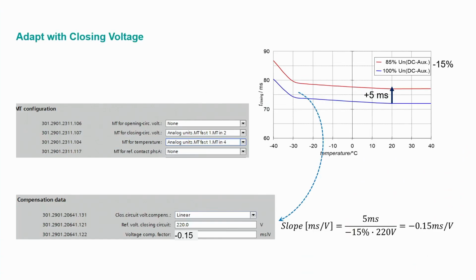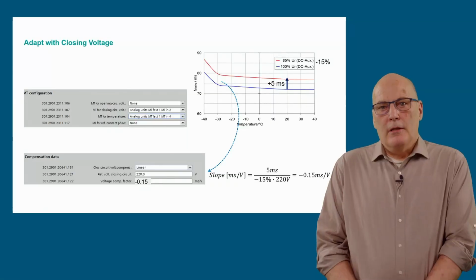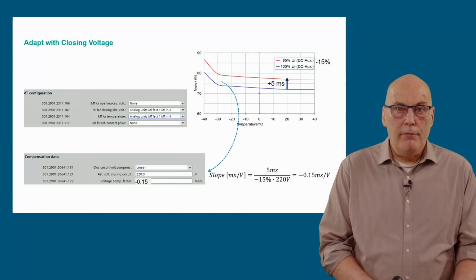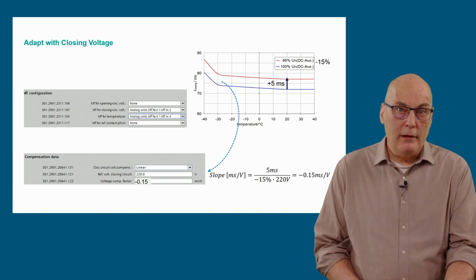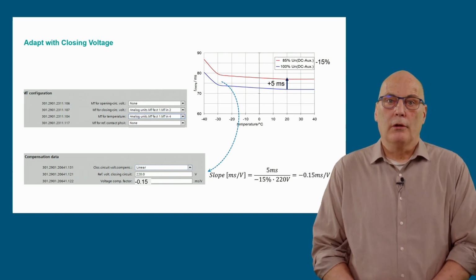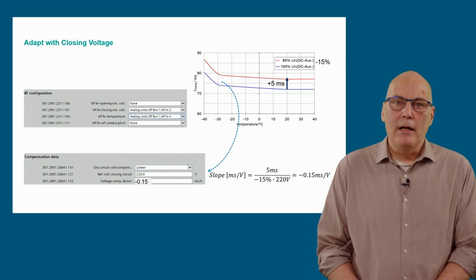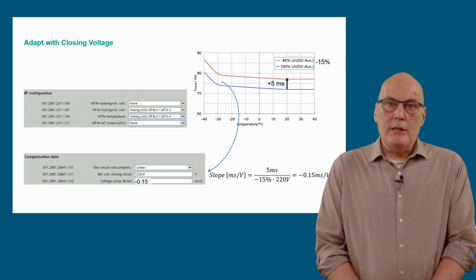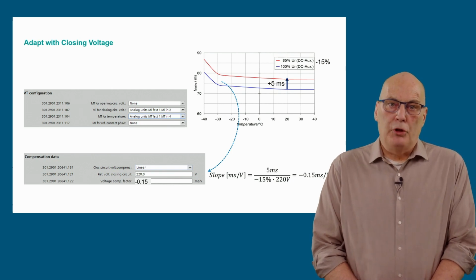So here in this slide, it is shown how the control voltage compensation is done. Select the corresponding transducer in top left diagram as before. Apply a linear characteristic in this case. The slope setting of the linear characteristic is calculated with the shown equation. The slope equals the delta time difference between extreme 85% closing and nominal voltage closing time divided by the voltage difference. It is best to do this at normal ambient temperature, e.g.